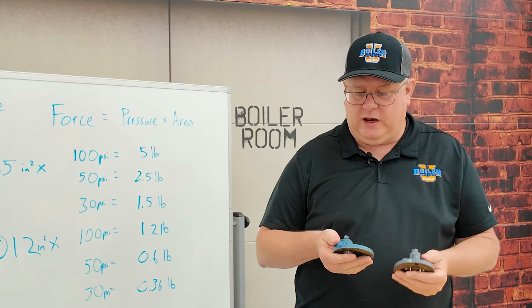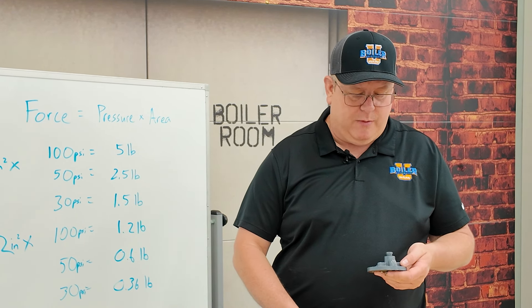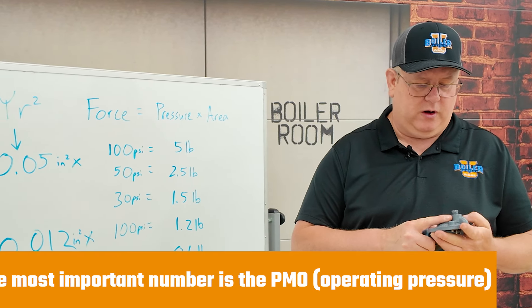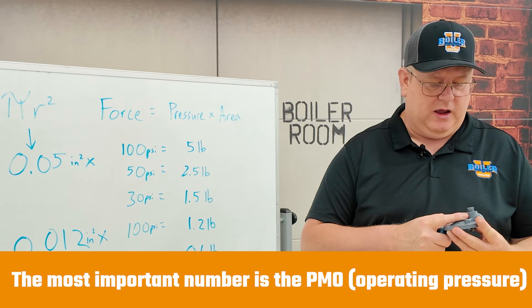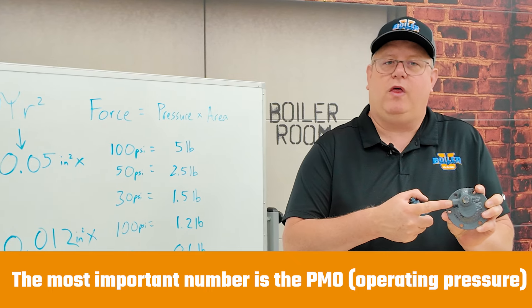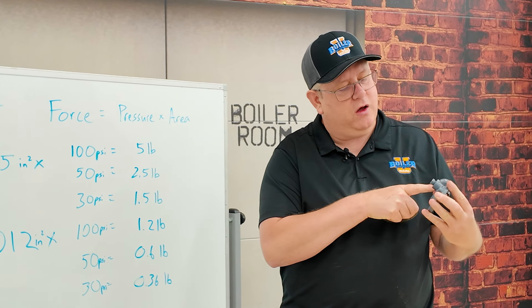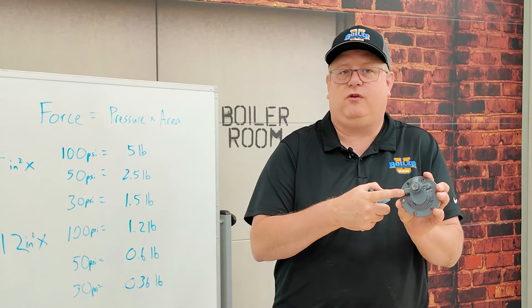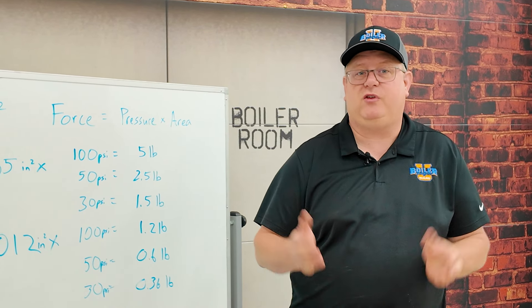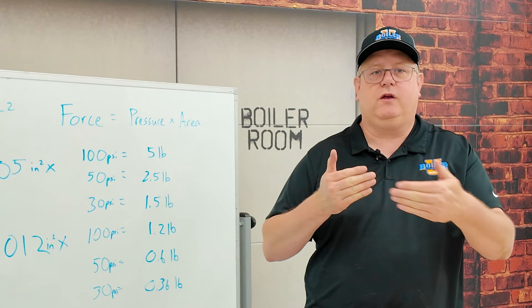When we look at a trap, it may have a maximum working pressure, but the most important number is actually the PMO, or the operating pressure. And that's actually a differential — because we're going to have pressure perhaps on both sides of that orifice.